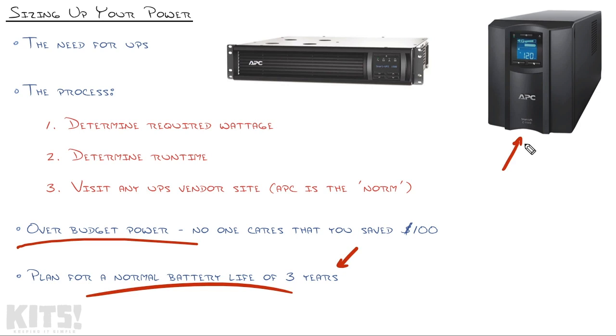Something you'll notice when batteries start going bad is they start getting hot. So if you have monitoring on your UPS, a lot of people have environmental monitoring, you can watch the temperature, and if it starts going up, you know the batteries have gone bad. The batteries will also swell in many cases if left unchecked. Even though batteries can often last longer than 3 years, in mission-critical network environments I'd suggest just replacing them anyway.